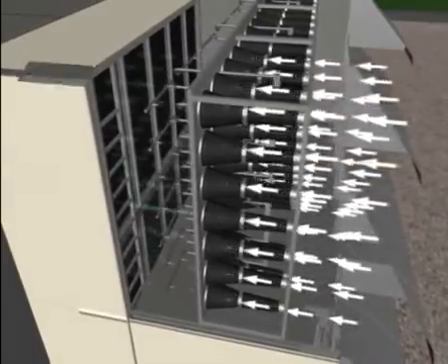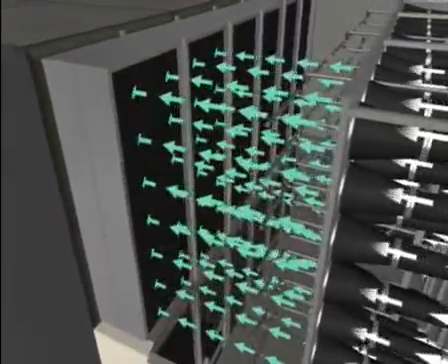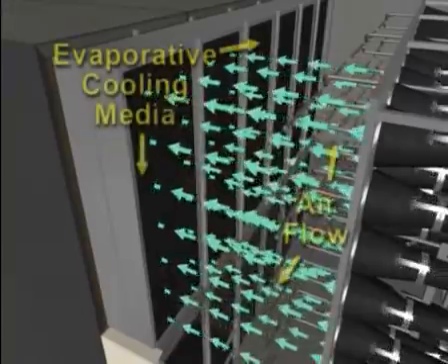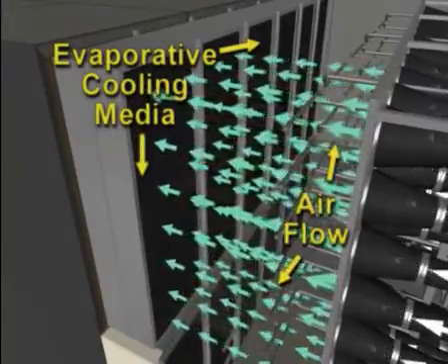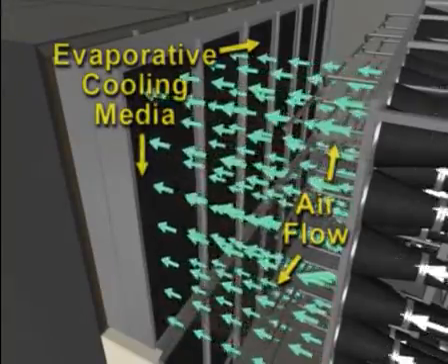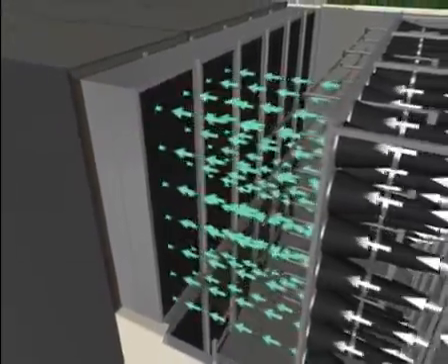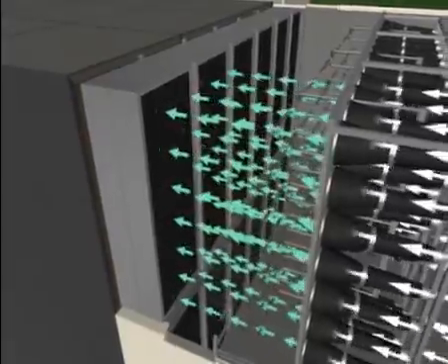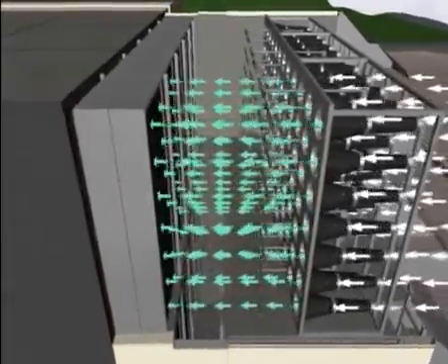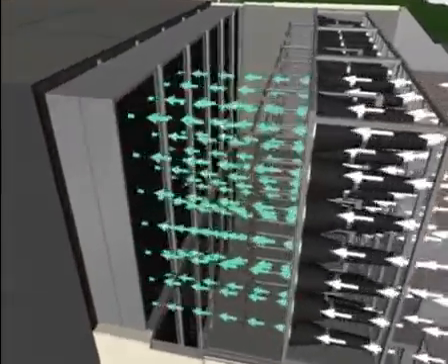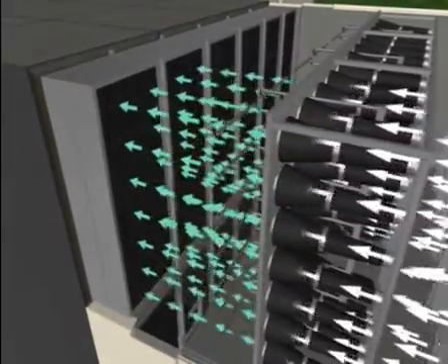From the filters, the air goes to an evaporative cooling media section. The evaporative cooler utilizes water to cool the incoming air. The cooler air results in a greater density of mass flow, thus maximizing the gas turbine's power output during hot days of operation.